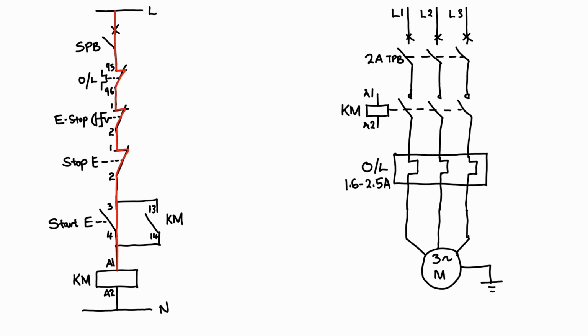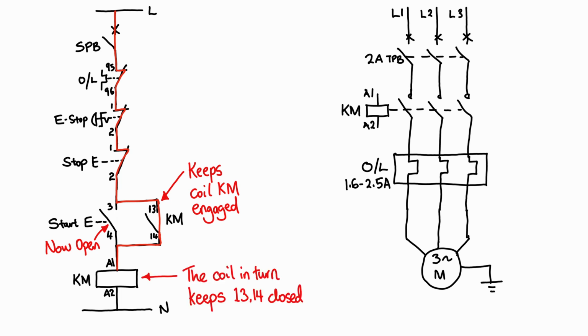As soon as this contactor is powered up, it engages, and it closes this contact here, 13 and 14. When it closes 13 and 14, it creates another parallel path of current. So when you release your finger from the start push button, this contact is going to open on the start push button, but our contactor will remain engaged. Why? Because we've already created another parallel path. This 13 and 14 will remain engaged, and that's why we call it the hold in or the auxiliary hold in, because it will maintain a path for the flow of current to our contactor coil as long as we keep that circuit switched on.